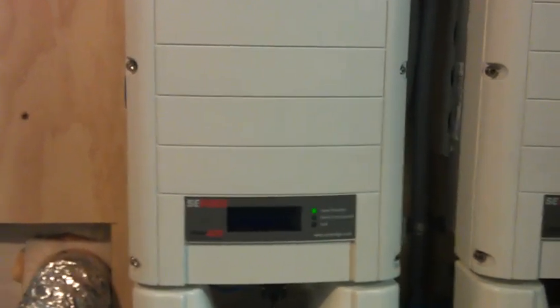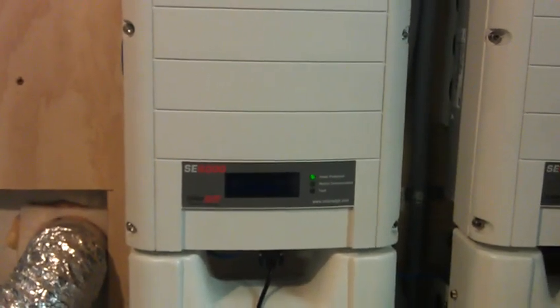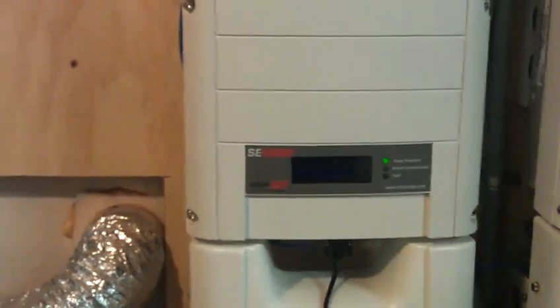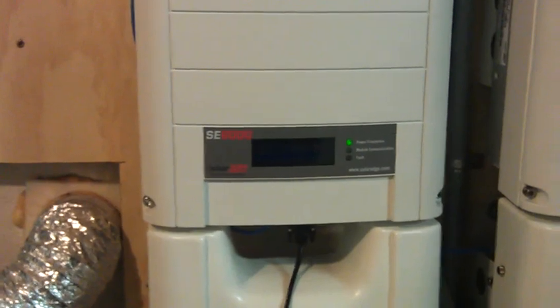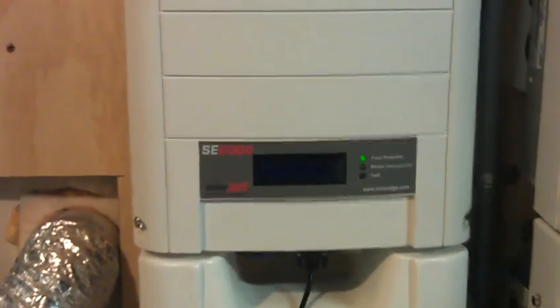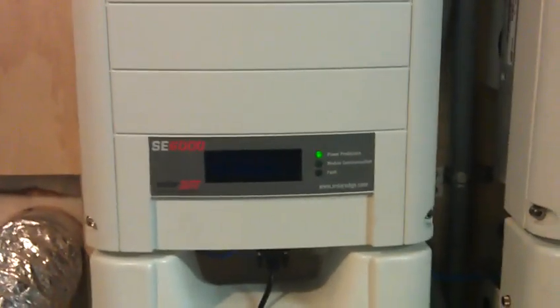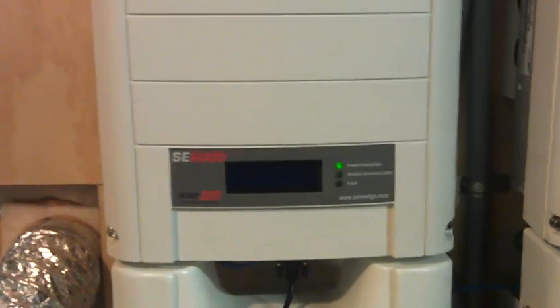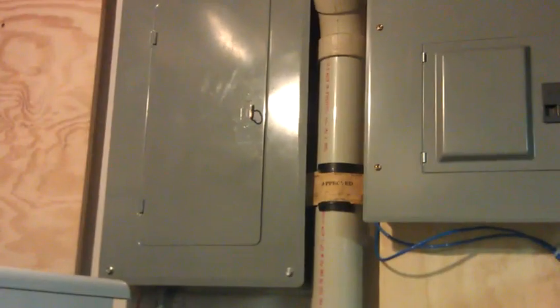Here we have our SolarEdge 6 kilowatt inverter. We hooked up 27 of the power optimizers there too, and as you can see, the unit is functioning. We've got power production and communication.